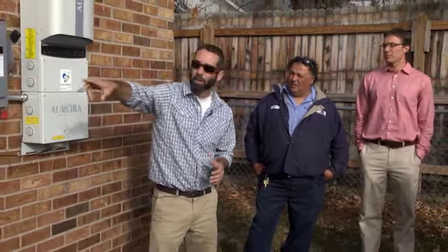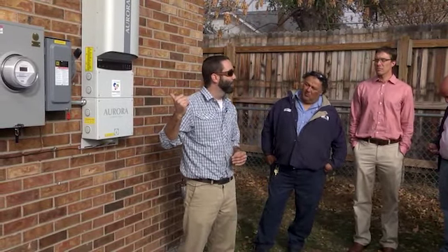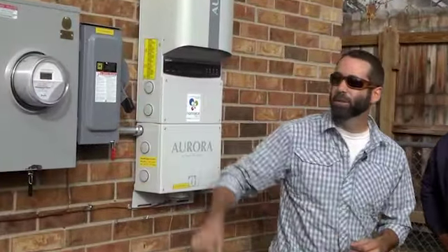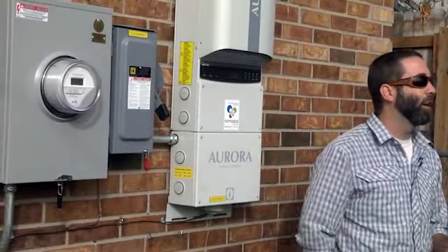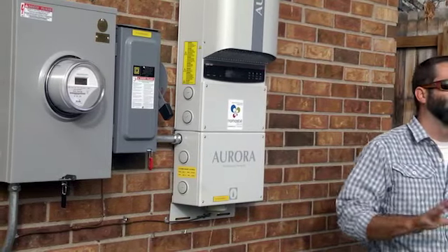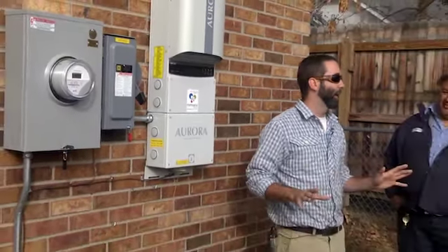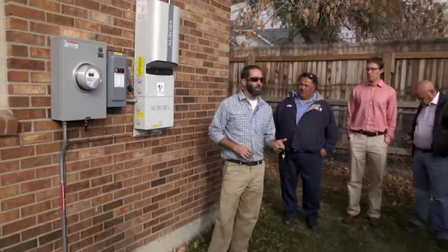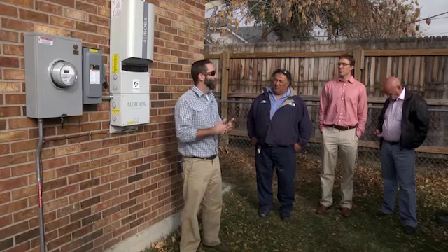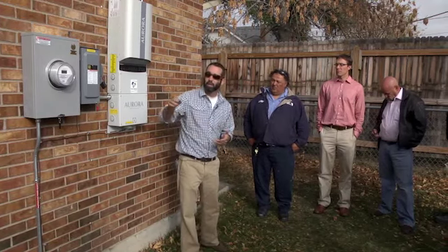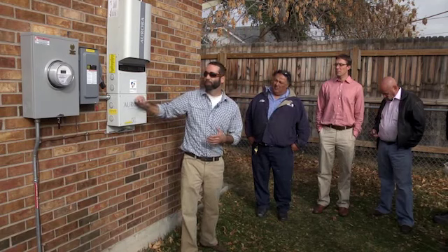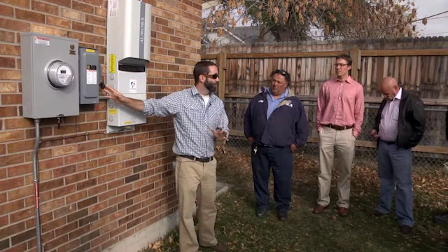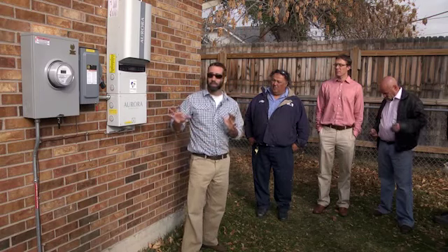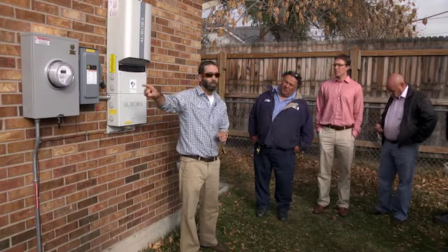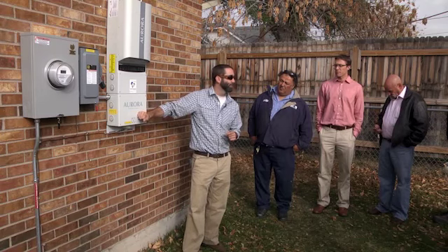So if I were to go, looks like we have a main breaker here outside and there's a load center inside. If I needed to replace a breaker in that panel, I would walk up to this, turn this off. I'd walk to the main breaker, turn that off, go inside and do my work. In that situation, you are completely isolated from the solar. There's no impact that the solar can have. In some cases, we interconnect into a unit through a backfed breaker. In that situation, if you turn off the main disconnect, the inverter will turn off regardless. This thing doesn't matter. However, it's best practice in this situation, if I were to turn that main breaker off right now, without turning this off, the inverter is still live.